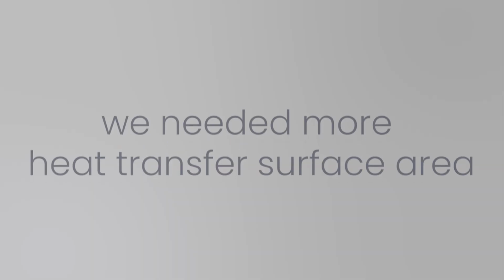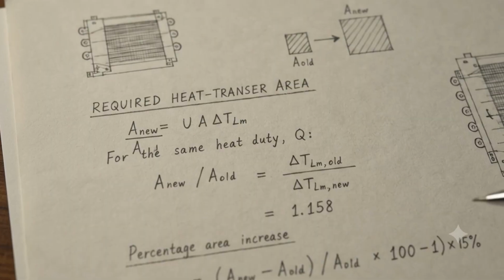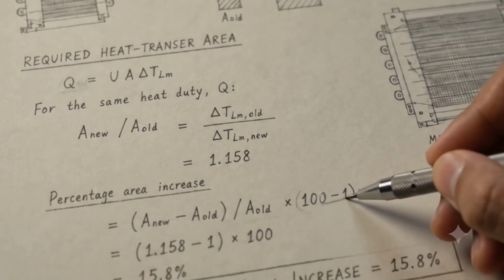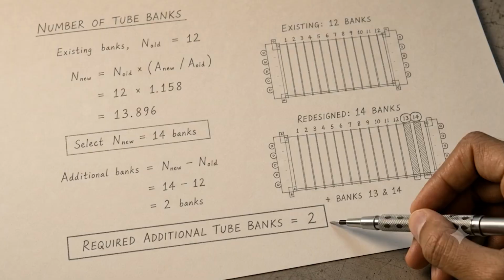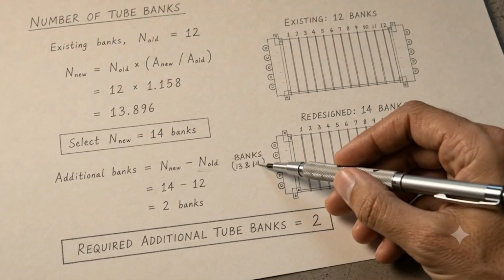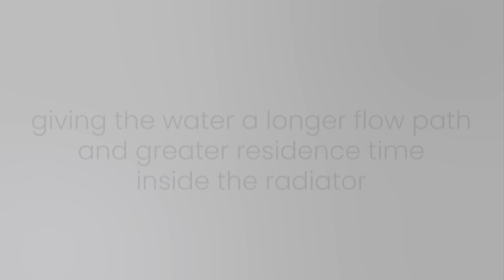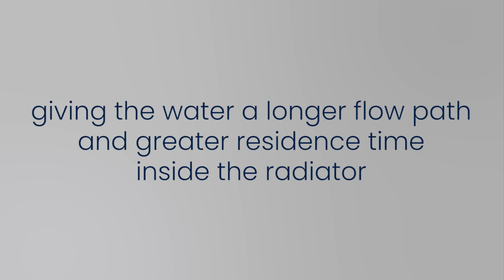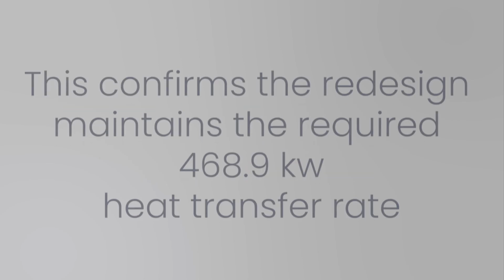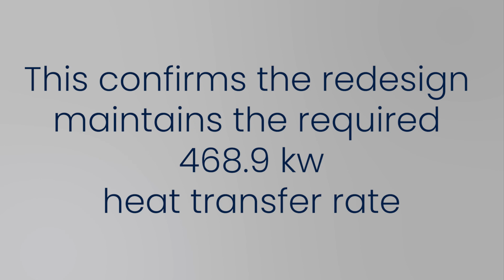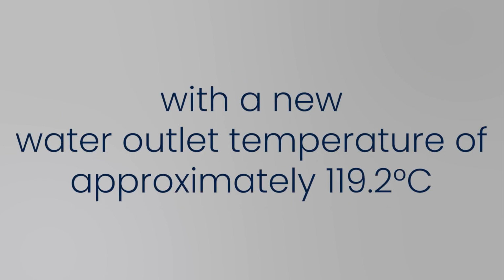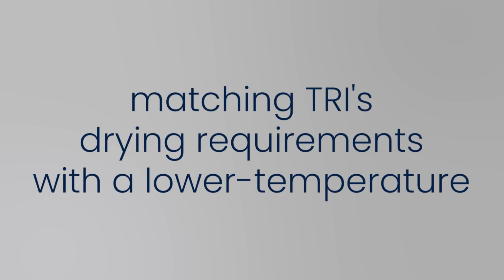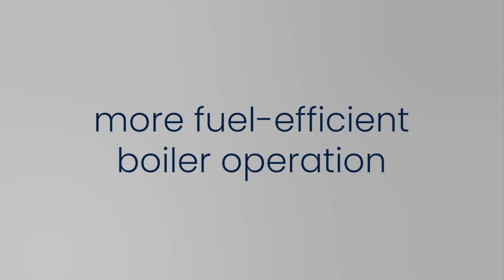To compensate, we needed more heat transfer surface area. Our calculations showed a required increase of approximately 15.8%, and adding 2 extra tube banks provides almost exactly that additional area, giving the water a longer flow path and greater residence time inside the radiator. This confirms the redesign maintains the required 468.9 kilowatt heat transfer rate with a new water outlet temperature of approximately 119.2 degrees Celsius, matching TRI's drying requirements with a lower temperature, more fuel-efficient boiler operation.